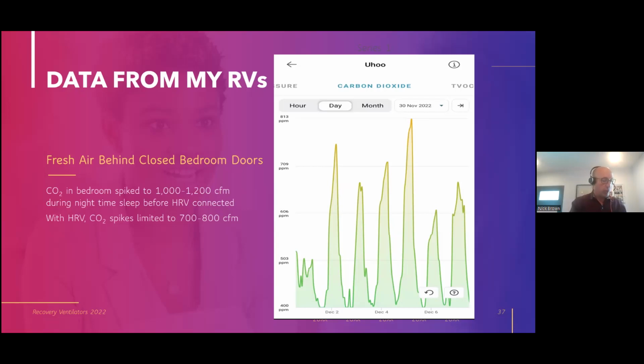And the last chart I wanted to show you, this is from the main house one. Remember I said ERVs with dedicated duct systems do a nice job of getting fresh air behind closed bedroom doors at night, which an exhaust-only ventilation strategy obviously doesn't. Well, this shows we're maintaining CO2 spikes behind our bedroom doors. This is my master bedroom, sorry, primary bedroom, under 800 parts per million. And that's after we installed a recovery ventilator fresh air duct in our bedroom. Before that, I saw CO2 levels spiking to 1,000, 1,200 as we slept at night. And, you know, studies show you're going to have a better quality of sleep if you can avoid those spikes. Hard to quantify that impact, but I think it's safe to believe it's there.